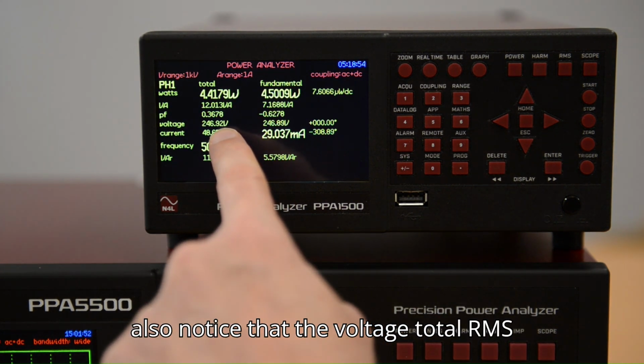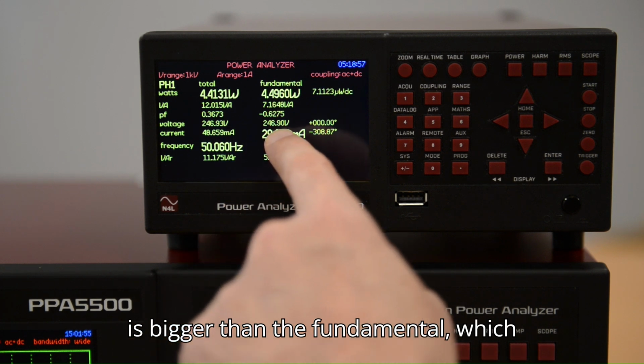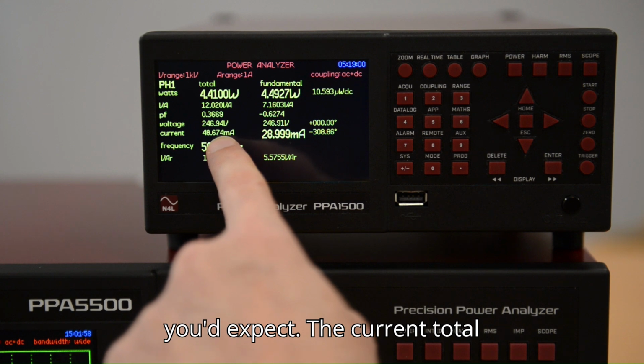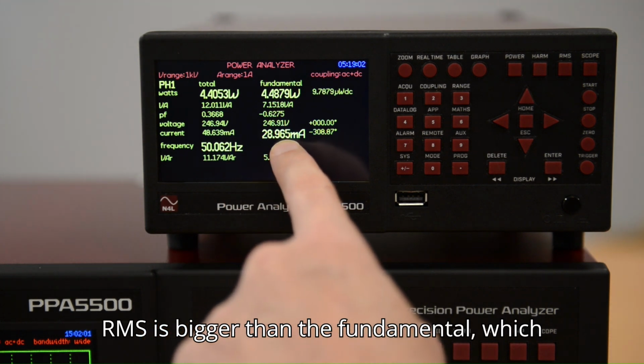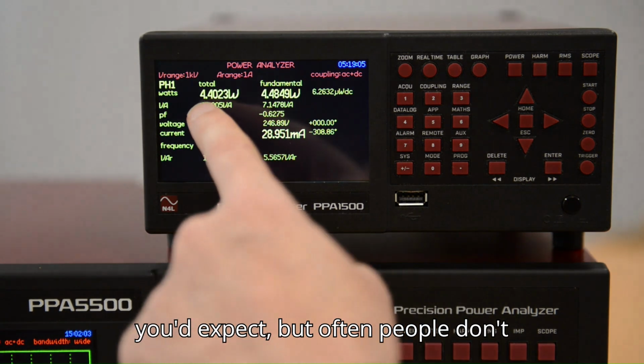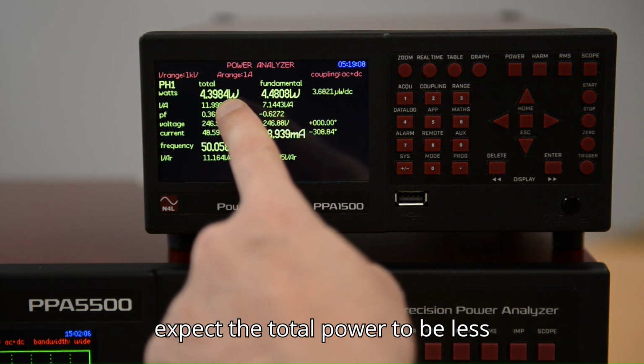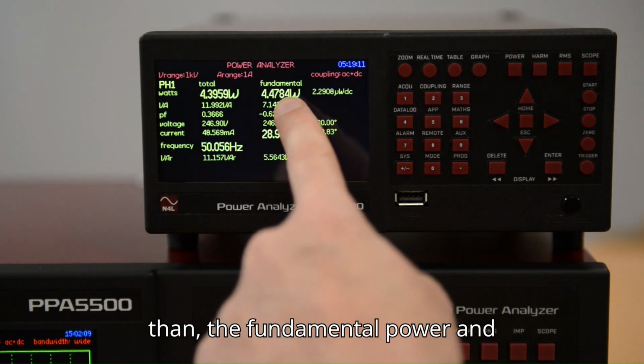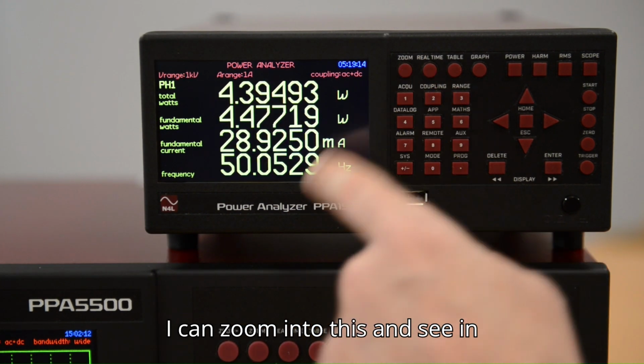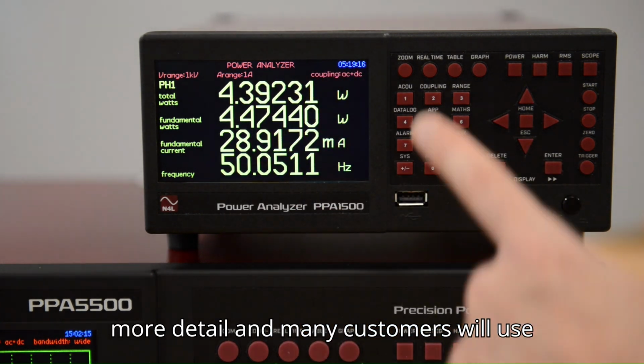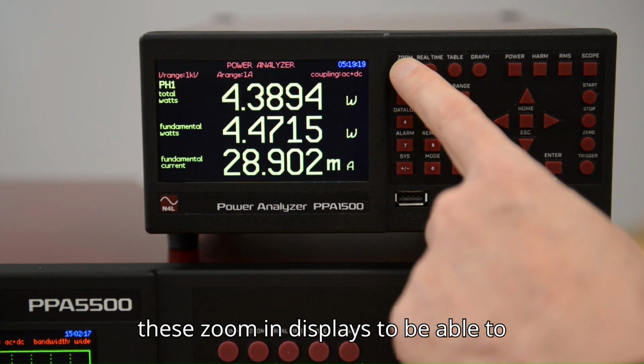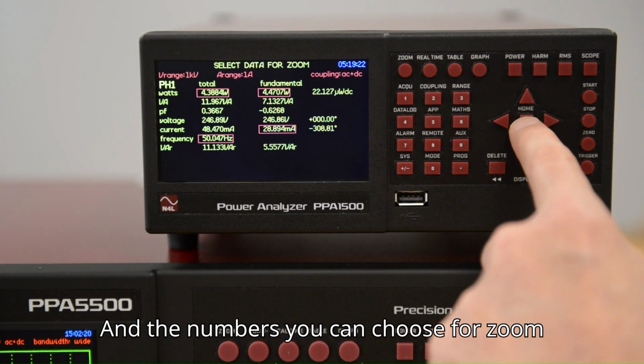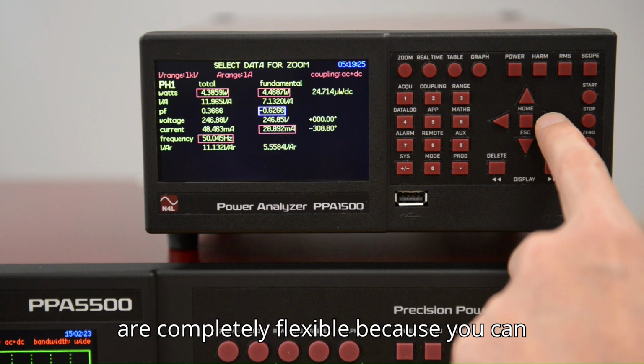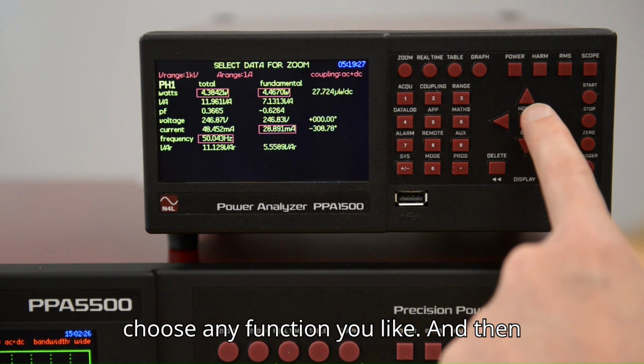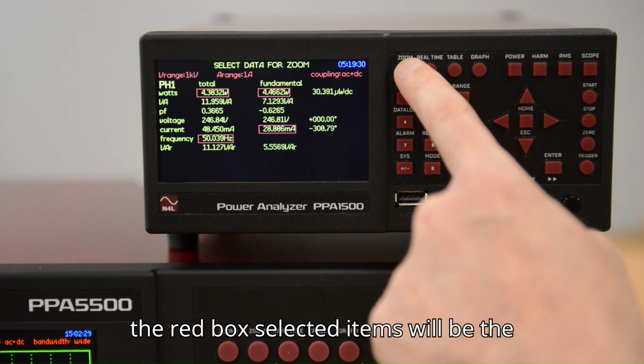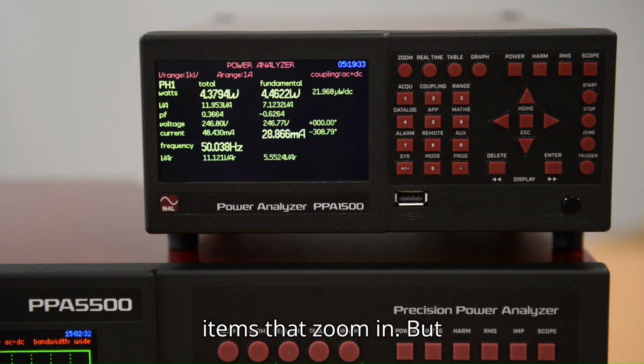You also notice that the voltage total RMS is bigger than the fundamental, which you'd expect. The current total RMS is bigger than the fundamental, which you'd expect. But often people don't expect the total power to be less than the fundamental power. And I can zoom into this and see it in more detail, and many customers will use these zoom in displays to be able to see numbers that they're interested in. And the numbers you can choose for zoom are completely flexible because you can choose any function you like. And then the red box selected items will be the items that zoom in.